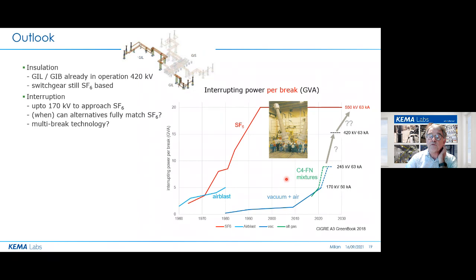Look at the graph at the right side, where the growth of the breaking power in a single SF6 interrupter is shown over time. Please note, we are speaking about the interrupting power per break here. You see that already by 1995, the maximum of 550 kV in a single gap was reached. When roadmaps announce 420 and 550 kV circuit breakers, it remains to be seen how many breaking units are needed to fulfill this task.